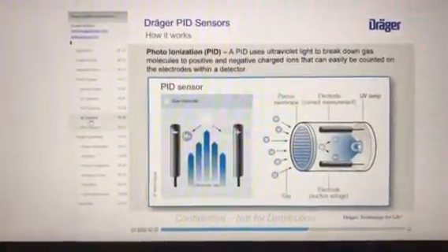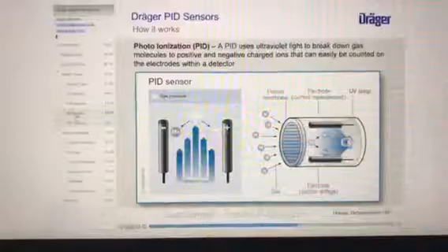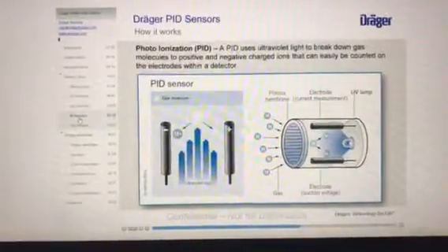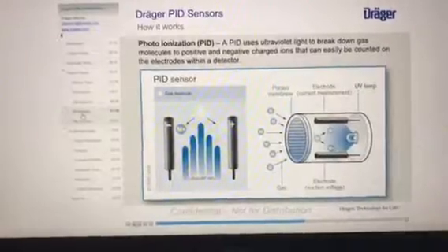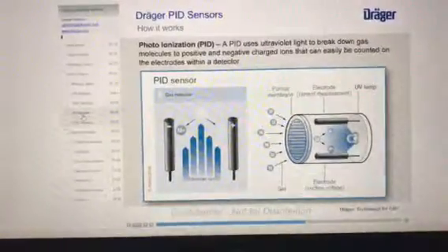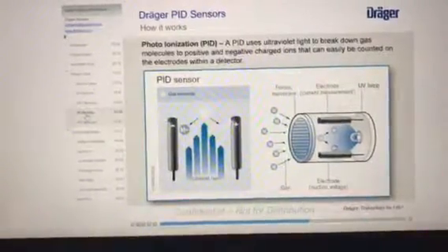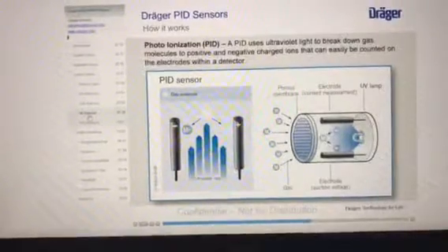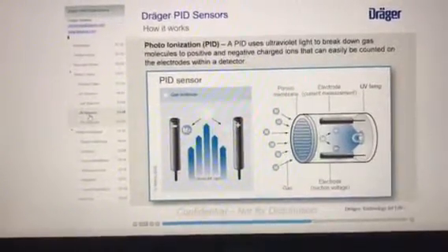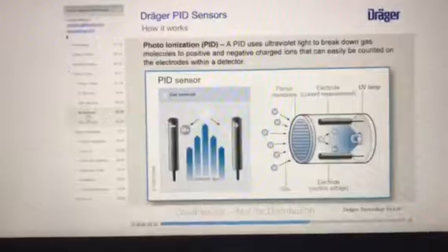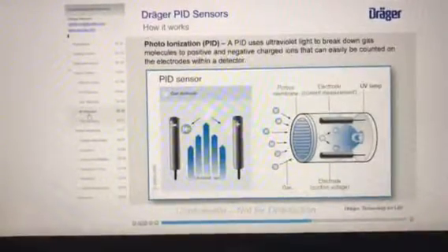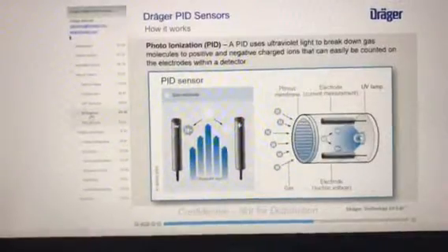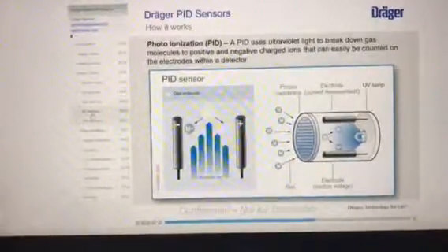The strength of this current is directly proportional to the concentration of ionized molecules inside the chamber, and this makes it possible to determine the concentration of harmful substances in the air. Keep in mind that this sensor becomes important for concentrations of combustible gases that are toxic at very low levels, which are reached much faster than the concentrations needed for explosions. This type of sensor can be found in your X-am 7000 instrument.